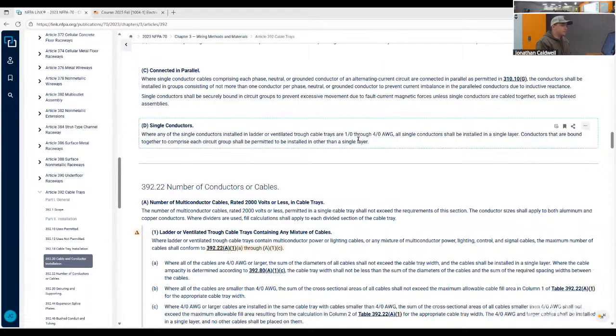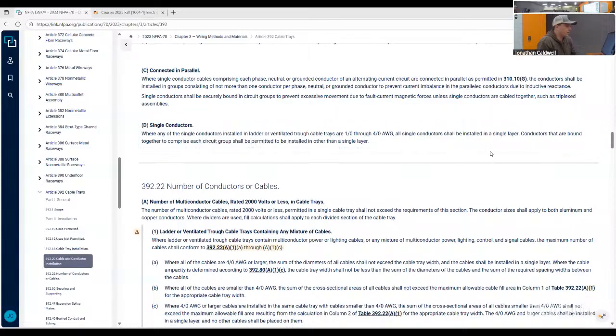And then connected in parallel, just follow the parallel rule. And then where any of the single conductors installed in ladder or ventilated trough cable trays are 1/0 through 4/0, all single conductors shall be installed in a single layer. Conductors that are bound together to comprise each circuit group shall be permitted to be installed in other than a single layer. So what does that mean, guys? They can't stack on top of each other. Exactly. So, perfect. If it's a single conductor run, it can't be stacked on each other. They have to be on the same layer.